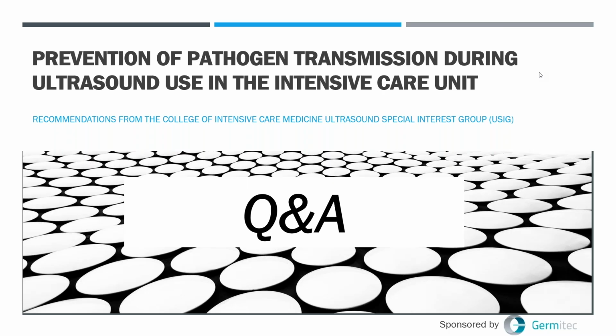Okay, thank you. We use Tegaderm as our probe cover to reduce cleaning and HLD or LLD after use based on procedure. This ensures we have a quick turnaround time. What do you use? We use sterile probe covers, yeah. So we don't recommend them. I mean, they provide an inconsistent barrier. They do probably minimize soiling, and they're not doing nothing, and they probably do increase efficiency with disinfection cleans. I think as long as you're doing a good disinfection afterwards, that's more important. But just don't overestimate the benefit that you're getting from a sterile cover.